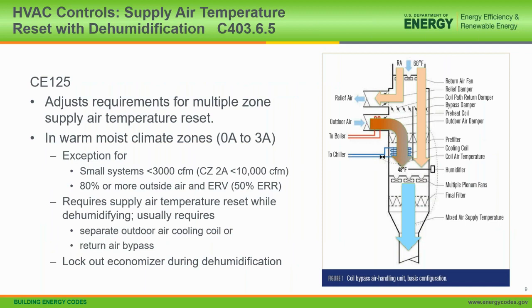HVAC controls for supply air temperature have been modified. Before, a supply air temperature reset was required in all zones for a VAV reheat system. What this does in the moister and more humid climate zones, the A climate zones from 3 down to 0, is require some special provisions so that the supply air temperature reset can continue to operate during dehumidification. The dehumidification is primarily of the outside air where the moisture is coming in. So there are a couple of ways to meet that. The code is not really specific, although the user's manual and informative notes suggest how to do that.